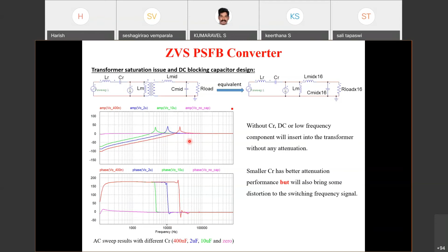If we reduce the value of the capacitance, it actually provides better attenuation for the DC components. This is a 400 nanofarad capacitance for a certain design, and this blue trace is a 2 microfarad capacitance. With the 400 nanofarad capacitance, your attenuation is minus 100 dB, which is good. But a challenge with smaller and smaller values of CR is that in the voltage response you see more ringing. So we need to arrive at a balance — maybe the blue trace is better than either the green or red. That's a design challenge you'll have to stick with.